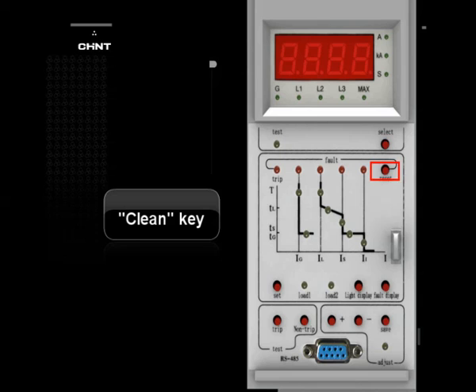Clean Key: Press this key to make the breaker normally operate after release of setting, test, fault, or data check.